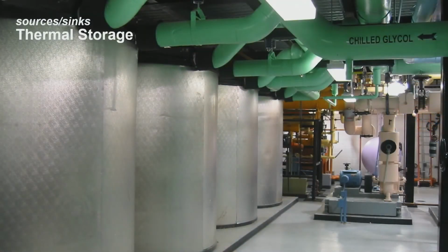Another option for finding BTUs is to use thermal energy storage. Let's take an office building, for example. During the heating season in the morning, the building exterior needs heat. You can make ice and store that in a thermal energy tank and use the rejected condenser heat to serve the heating loads. As the building warms up during the day, you can melt the ice to serve the cooling loads. This will be an example of a storage source heat pump application.